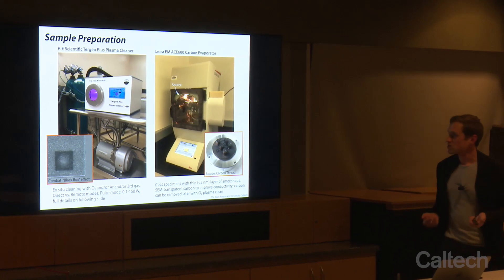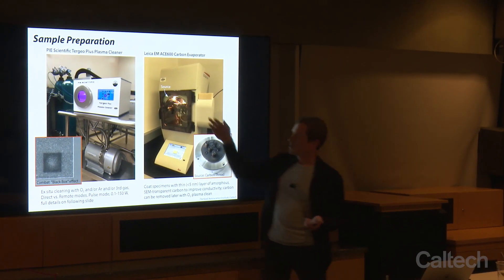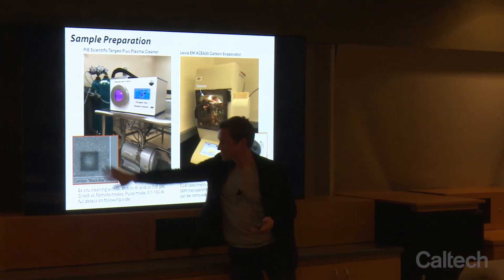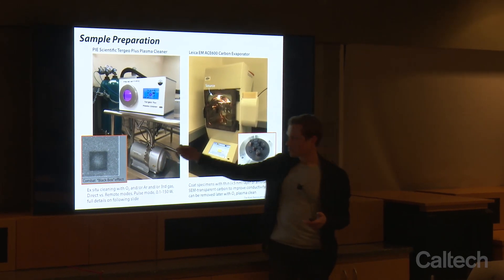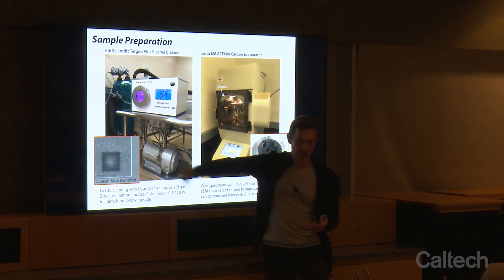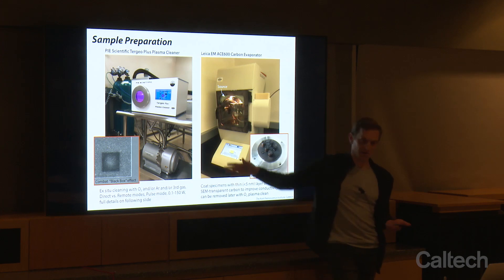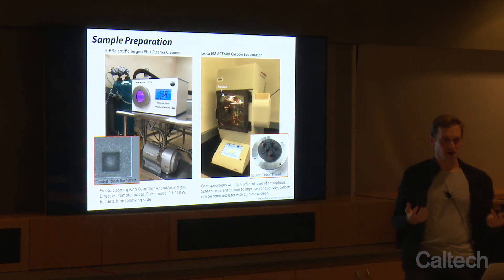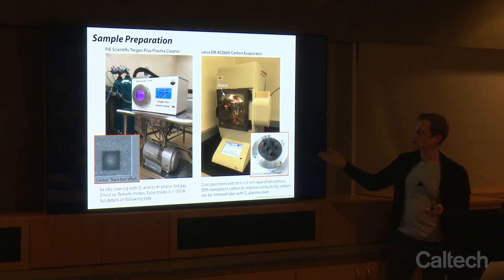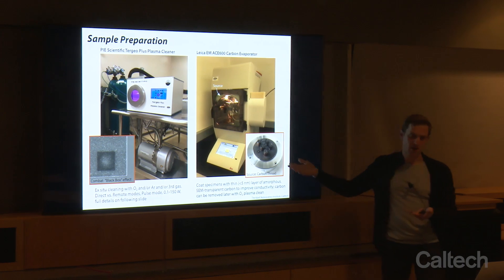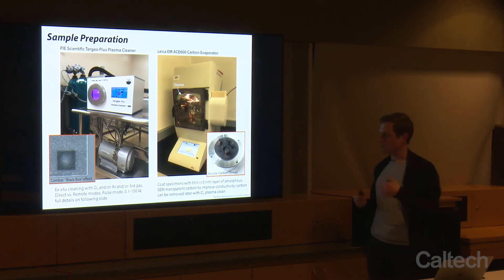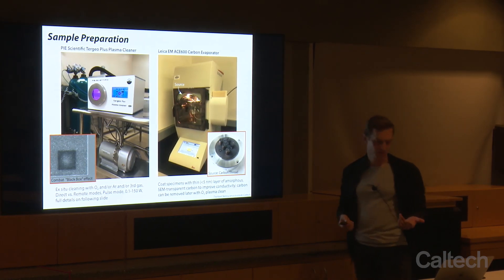In terms of sample preparation, we use an oxygen and argon plasma cleaner to remove organics from the surface of your sample. That combats what we call the black box effect, where organic material can evolve from the sample and get chemically vapor-deposited back on as a new thin film of carbon, which doesn't give off as many secondary electrons and appears darker. If you have a non-conductive specimen and can afford to, you can coat it with a carbon evaporator — just a few nanometers of carbon works both for imaging with the SEM and for making your sample conductive for use with the gallium-focused ion beam.